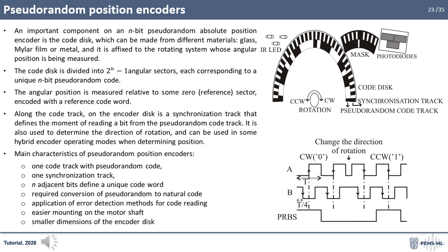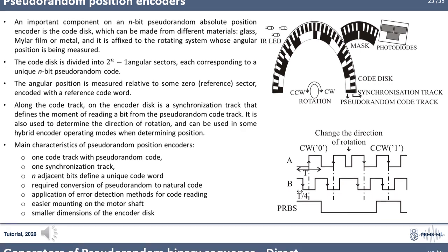Main characteristics of pseudorandom position encoders are: 1 code track with pseudorandom code, 1 synchronization track, n adjacent bits define a unique code word, required conversion of pseudorandom to natural code, application of error detection methods for code reading, easier mounting on the motor shaft, and smaller dimensions of the encoder disk.